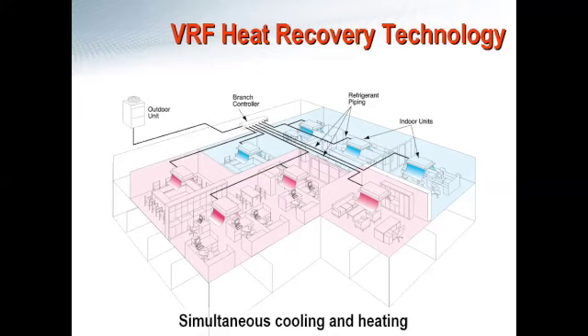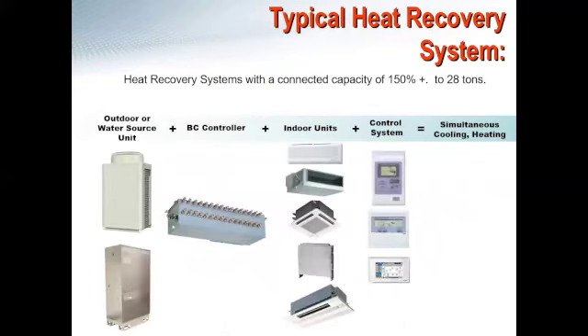So back here, again, we have all of these same indoor units and outdoor units on both the air and water side for both heat pump and heat recovery technologies. Really, the only added ingredient is going to be that BC controller, and the control system is going to act identically. So you can have this system controlled by local thermostats, either a smart thermostat, as you see in that second one down, or that localized or centralized controller tied into your BMS system.